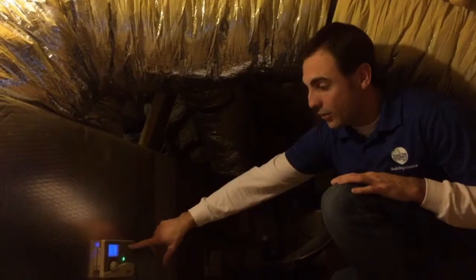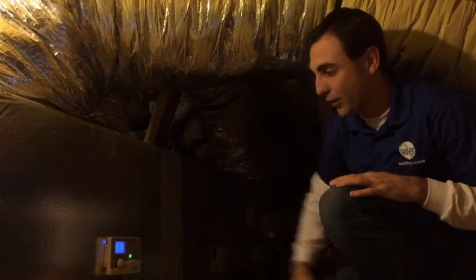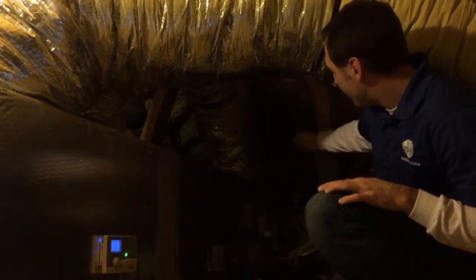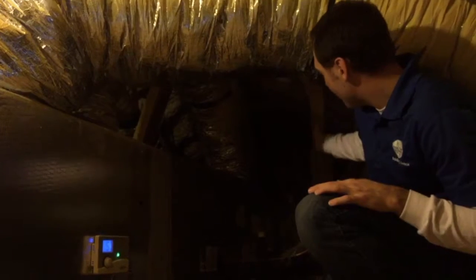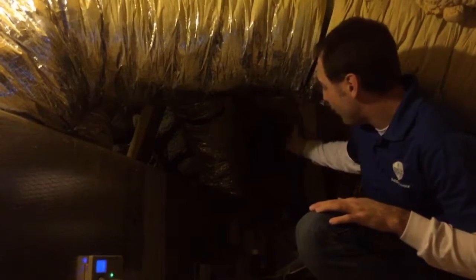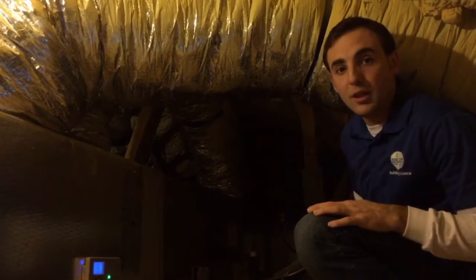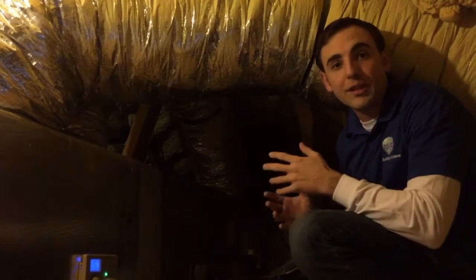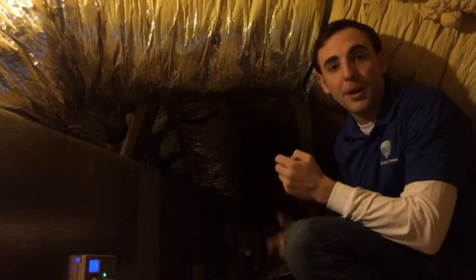So that's the first thing I do, is I look around the system and see what's going on. This one in particular has a fresh air controller here, and it actually has two zones. There's a damper that separates one side of the supply plenum that goes downstairs from the other side, which goes upstairs. So it's important to know all of those things and see the bigger picture before you start measuring the airflow. Now that we've looked at the existing ductwork and where the air comes from, we're going to go downstairs and look at where the air comes out. We're going to measure it and look at different ways of measuring airflow.